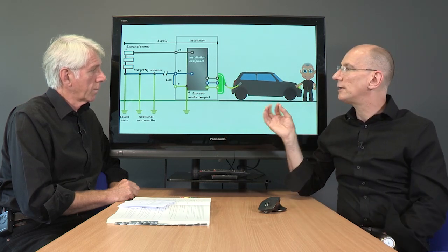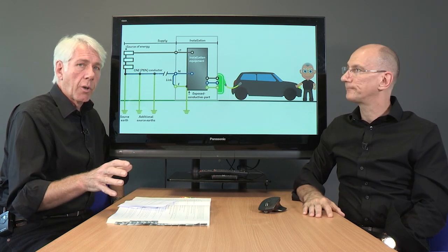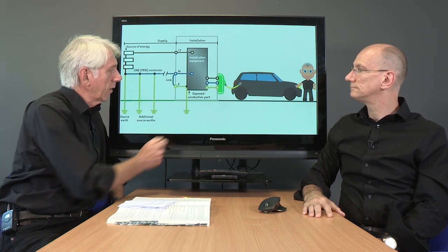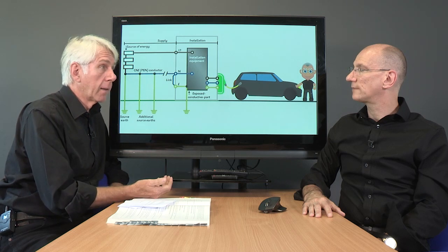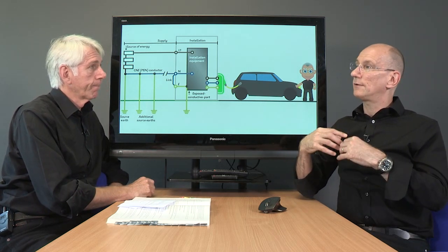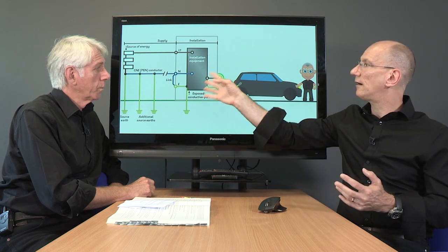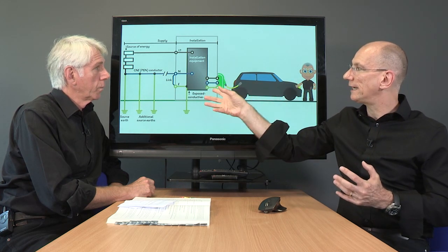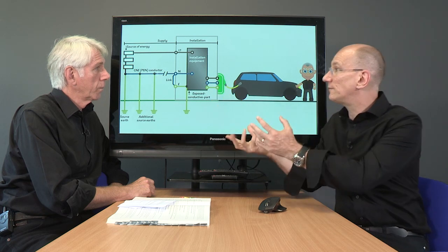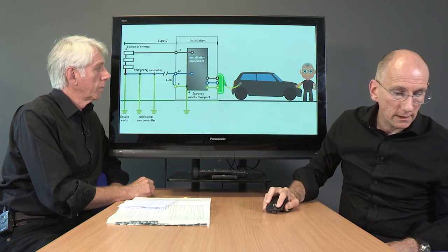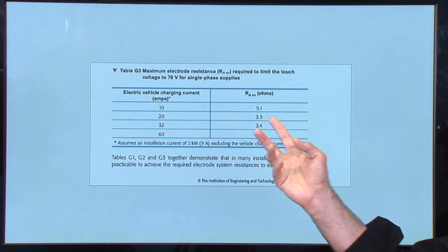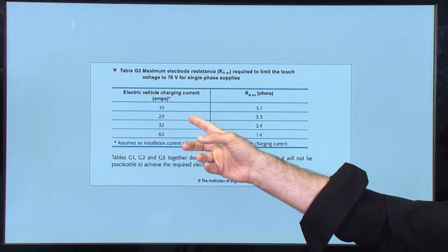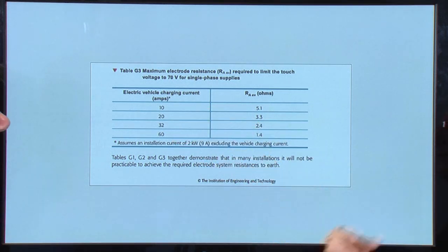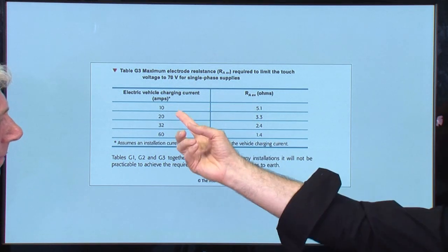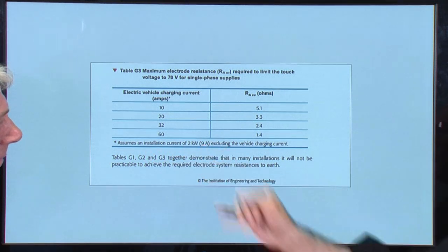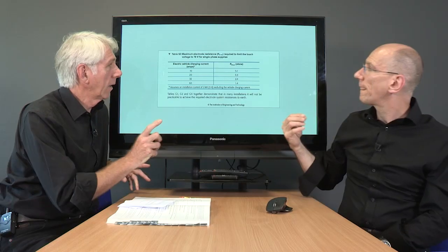So it's something that helped mitigate the risk. Now, all the discussion that's going on out there is to say that where we've positioned that wouldn't necessarily be the place where people are putting it. Well, having been told about these videos, I think they are trying to move away from this because it's quite difficult to achieve the values. When you look at the IET's code of practice, which is still very good by the way, it talks about the current and the loading of this installation. If you look at the values, if you've got 10 amps, which is basically just over 2 kilowatts, so it's an assumed load here. And that's a low charging current.